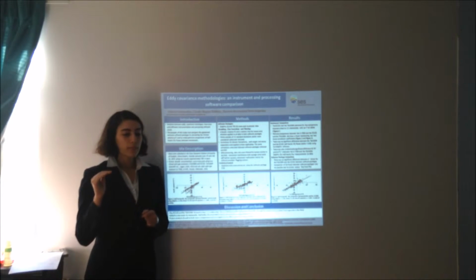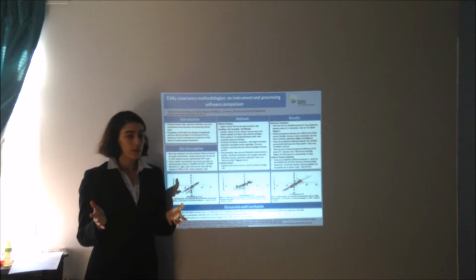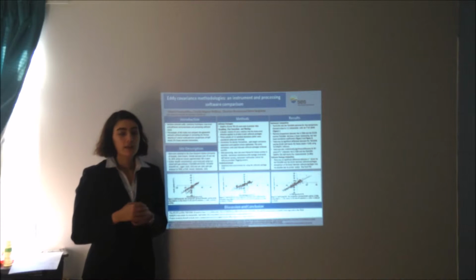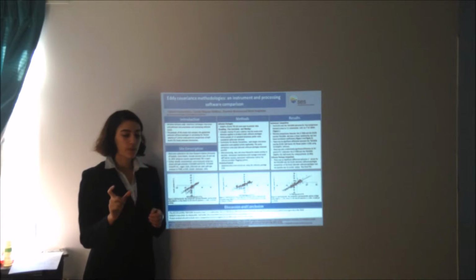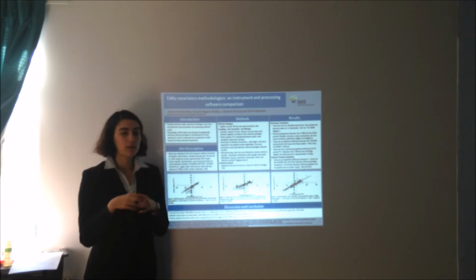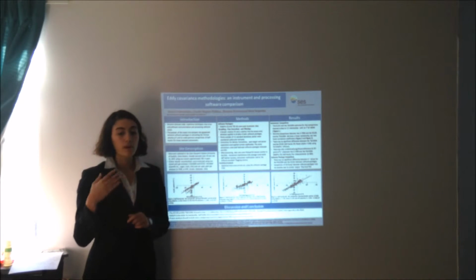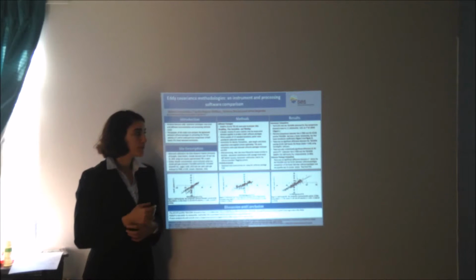So anytime where the instruments weren't working, where the software packages had flagged the value, where there was somebody working in the field or someone working on the instrument, those times were taken out and weren't used in the comparisons. After that, the data was compared using paired t-tests, so anytime where there was a value from the same instrument being processed with different software packages, or different instruments being processed within the same software package at the same time period, those values went through a series of paired t-tests, and we also ran a linear regression.